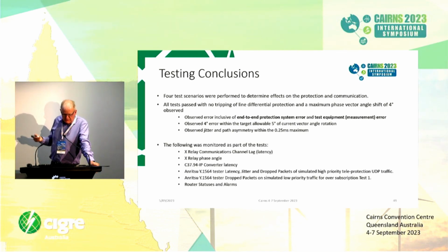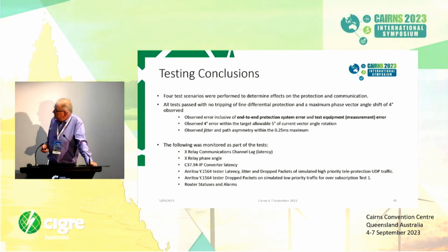So the following was monitored. As I said, we monitored the X-communication, X-relay channel lag, the X-relay phase angles via the injection test sets, the C37.94 IP converter latency, the Anritsu Y.1564 tester latency, jitter, dropped packets, etc. And the router statuses and alarms were also monitored.